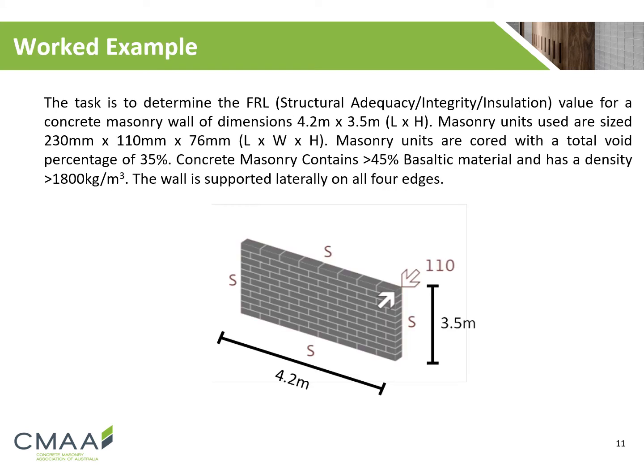To put it all together, we're going to quickly run through a typical FRL evaluation of a masonry wall. The single-leaf concrete masonry wall has dimensions 4.2m x 3.5m. The units used are the standard brick size 230mm x 110mm x 76mm, cored with a total void percentage of 35%, a basaltic content greater than 45%, and a density greater than 1800 kg/m³.